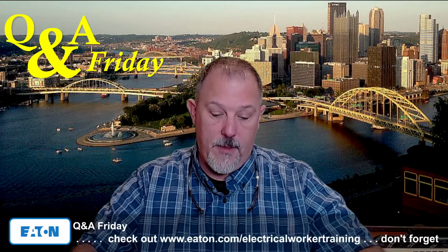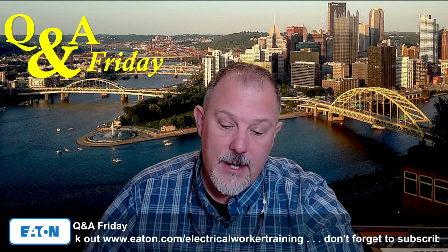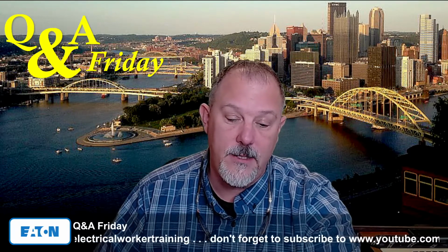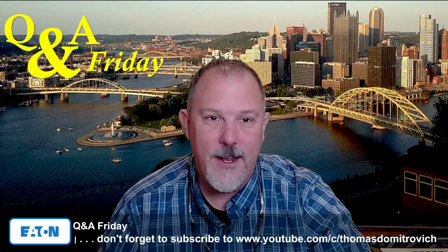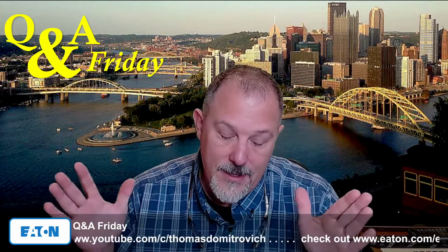And so what did we do? Well, we rerouted that, and I think our latest design, and I've been out of the product line long enough that technology has taken over, and I'm sure that a lot of what I remember about these designs has changed. But I know at one iteration they relocated the routing of that conductor, and everybody was like, "Wow, what did you do to your breakers? They're cooler." And you know what I say? I say, hey, yeah, we addressed your concern. We made a design change. We rerouted the conductor. Same length of a conductor, just a different route through the breaker.